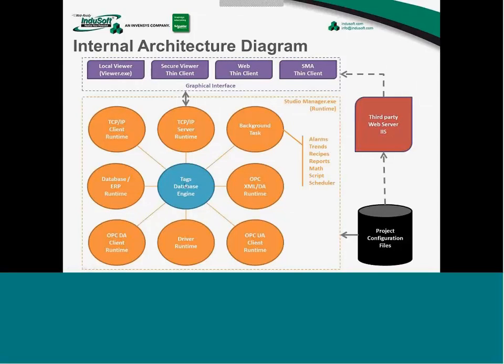The tags database engine, being the core of Studio Manager, is aware of any tags used at this moment by any other task. So if you configured a particular tag in an alarm worksheet, as soon as the tags engine receives a tag change from the driver, for tag X, for example, the tags engine sends a message to the background task indicating tag X changed value. And then the background task creates the alarm. The online alarm, the history alarm, depending on your configuration.